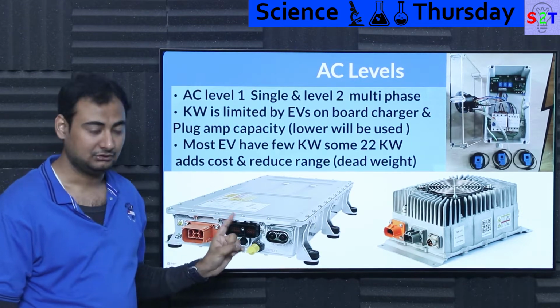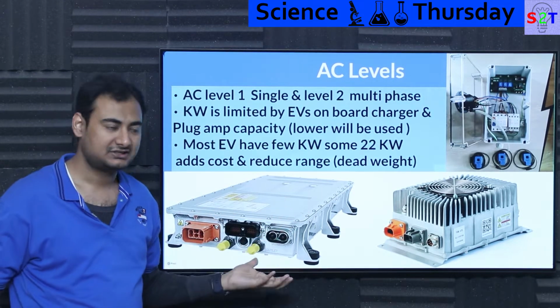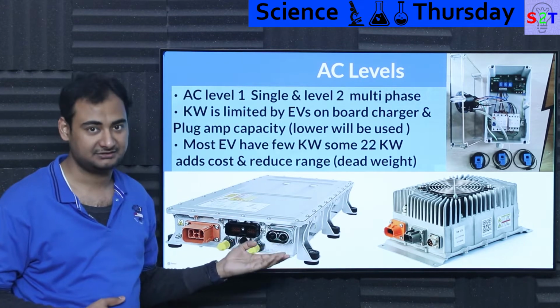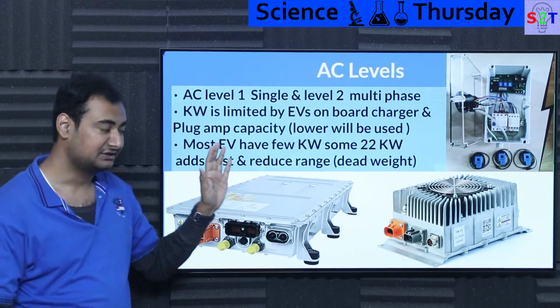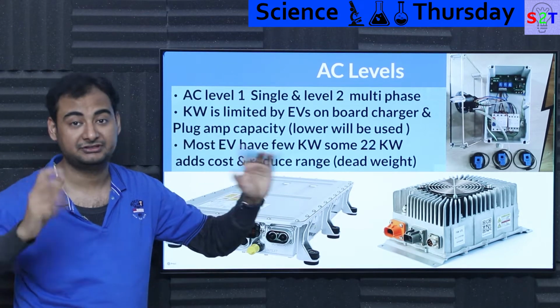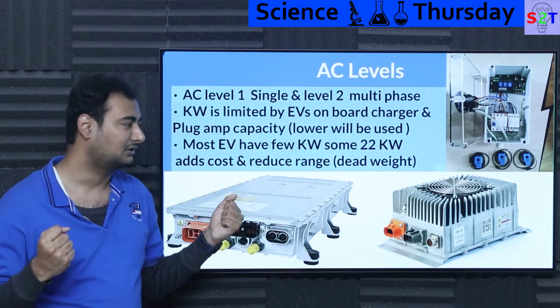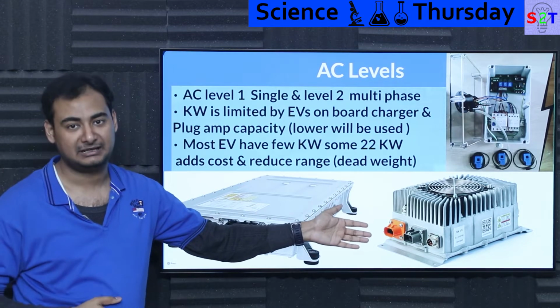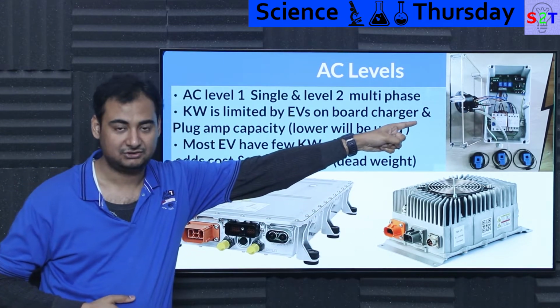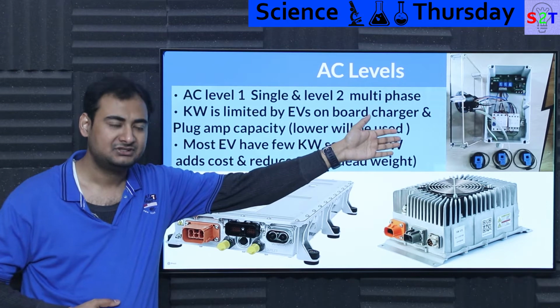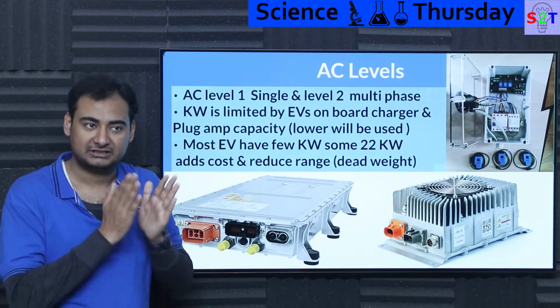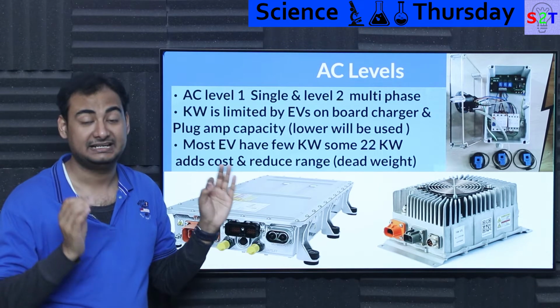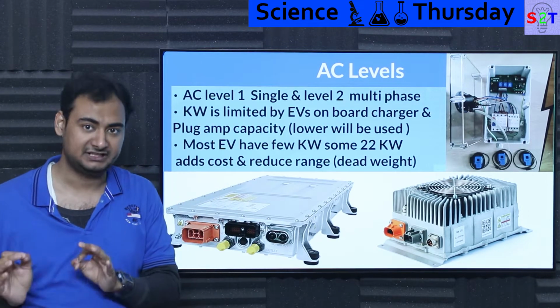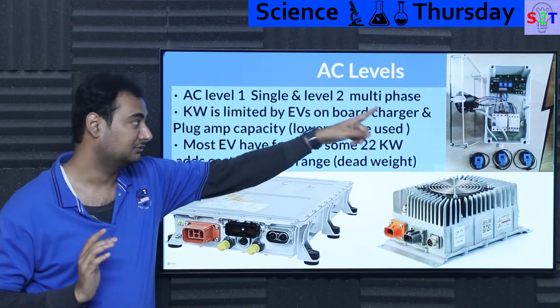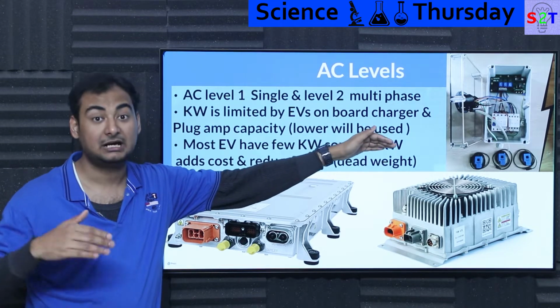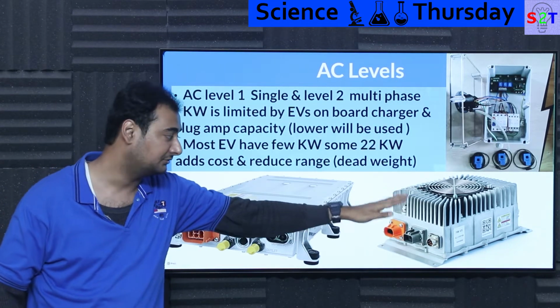These chargers are not the latest and most powerful because they have severe penalties, I'll explain further. Generally it'll say, hey, I can accept, let's say, 10 amps. Then it talks to your level 2 charger and asks for 20 amps. The charger may have its own memory where, if installed correctly, it says do not draw more than 15 amps per phase, or you can cause melting. So it tones itself down to 15.